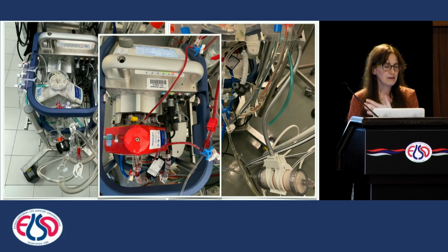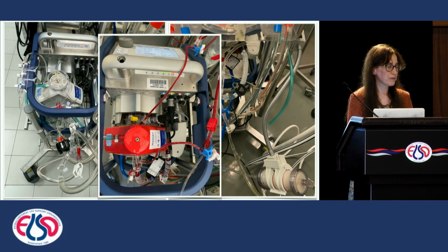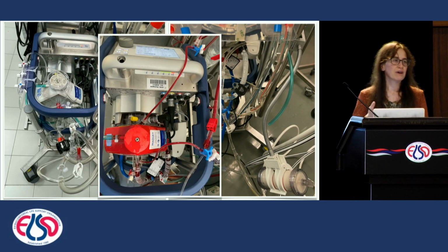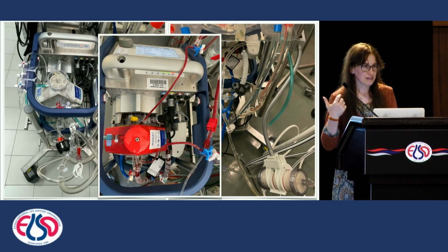A basic circuit, again, same machine, different circuit, could be easier to be managed by your staff and easier to be prepared. So you need to consider what you need for that particular patient and adapt the protocol you have defined in your center to that particular patient. What I always add also to a basic ECMO circuit are a couple of sampling lines before the oxygenator and after the oxygenator, which I also use to check the pressure if I have any doubt about the reading of the pressure integrated in the circuit.